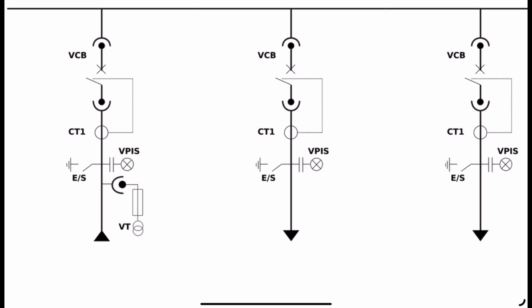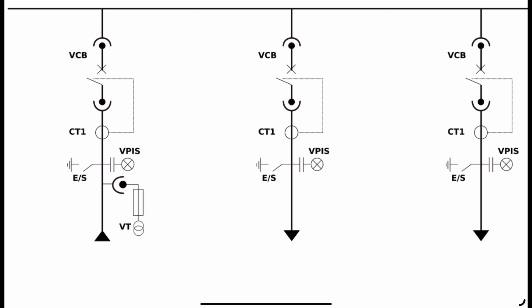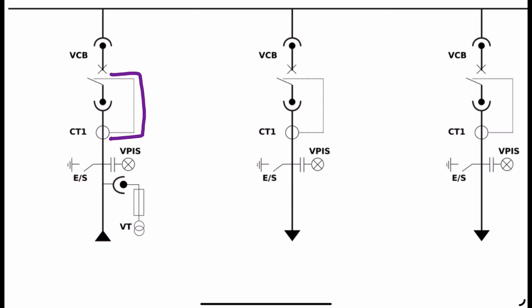Moving on, we have a current transformer — the simple circle symbol represents a current transformer. Just like the voltage transformer, the CT helps us measure the current flowing into the system and also provides protection if needed. You will also notice a connection going from the current transformer towards the circuit breaker — that input goes to its trip coil, and based on that, the circuit breaker can trip.